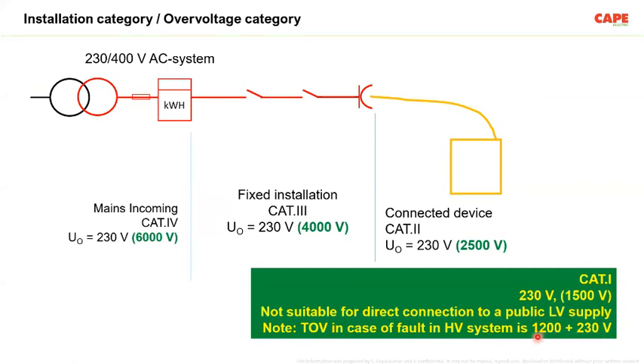So the actual voltage between earth and a phase conductor can be anything, 1430 volts up to 5 seconds. This is allowed in the standard. And the utility is not supposed to send more than this voltage into a consumer premise. So this is very much there.